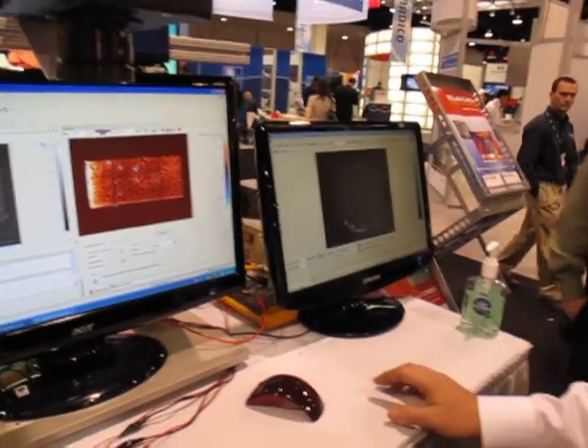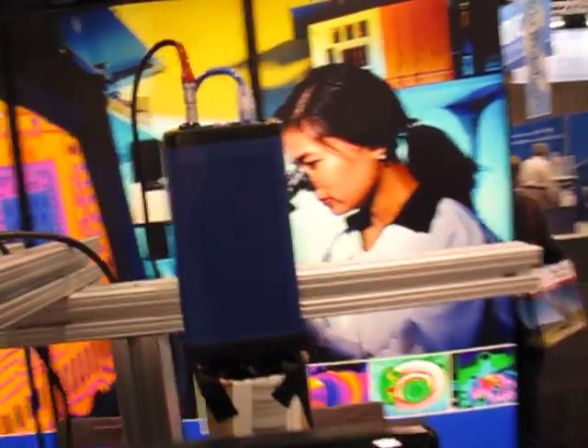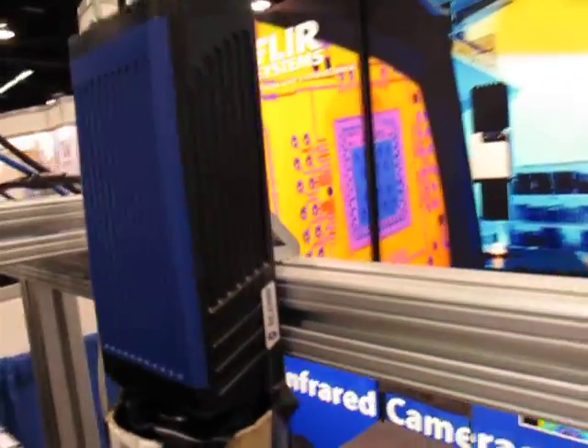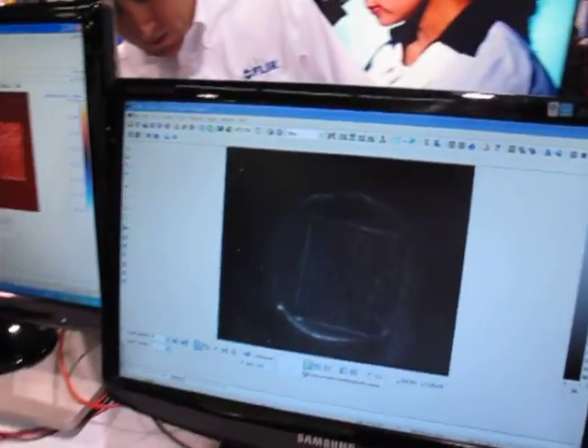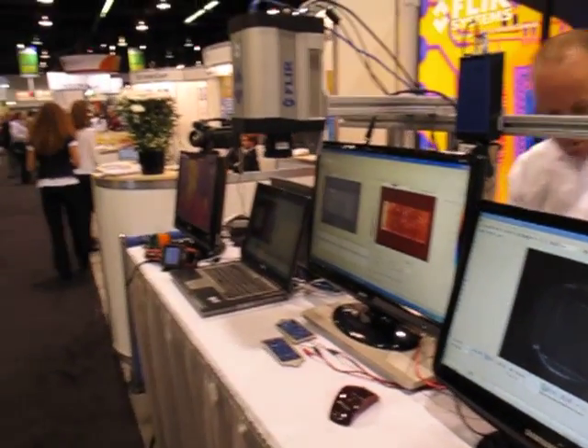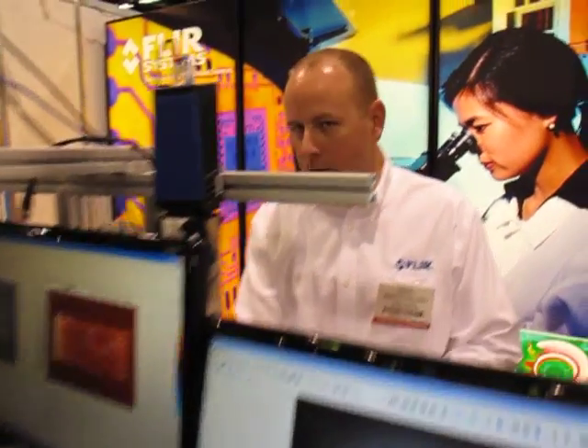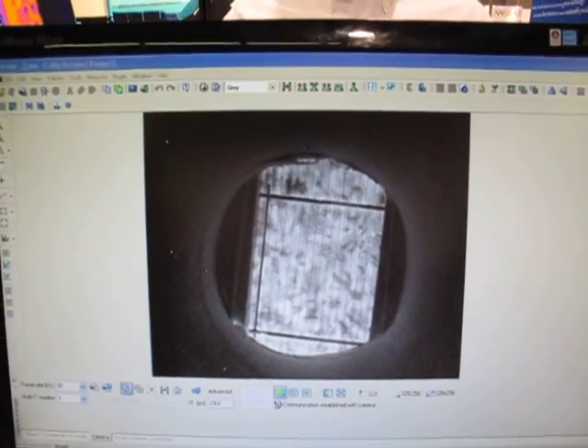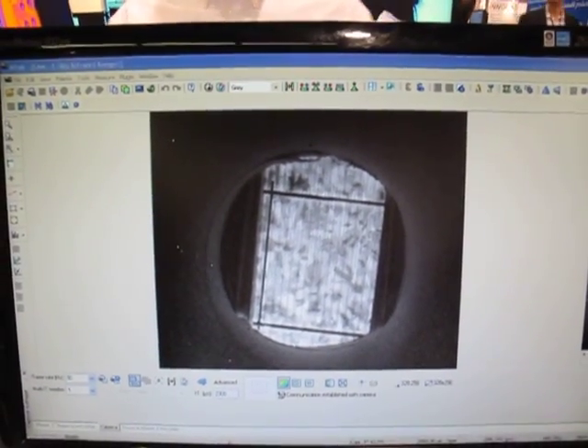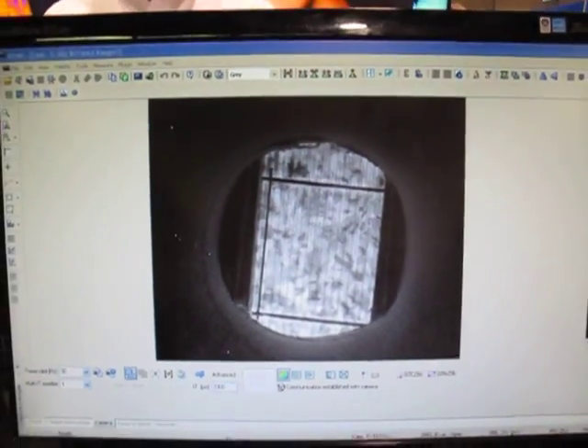And finally, the last test that we're doing is an electroluminescence test. Here we have our new SC2500 near-IR camera, and we have a power supply wired in series with the cell. We're basically going to operate the cell backwards in this case — instead of photons in and electrons out, we're putting electrons in and getting photons out. But the photons are coming out in near IR. So you can see the image on the screen here. If we turn it off and turn it on, you see it reappear. And there's a dark spot up near the top showing an area where the photons are not being effectively converted into electrons and vice versa.